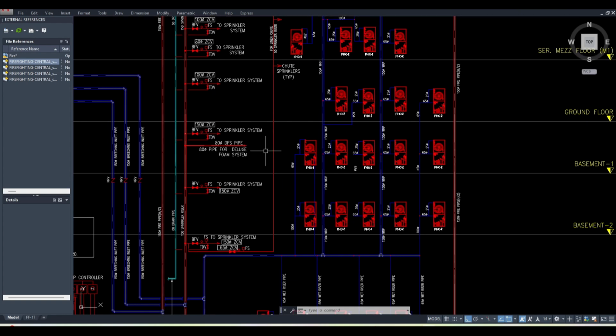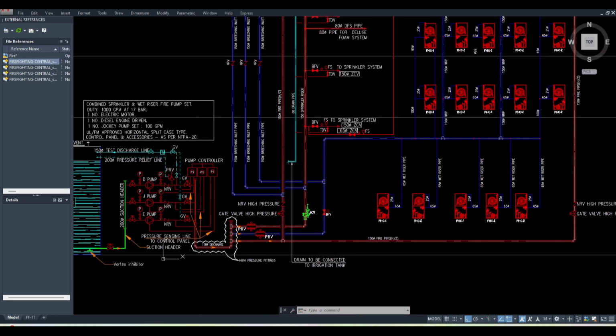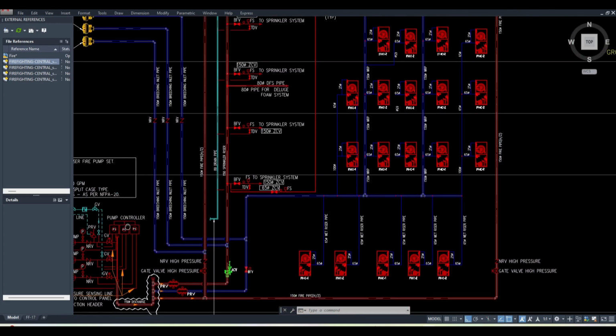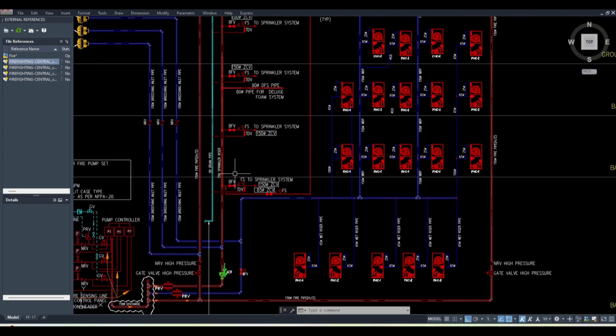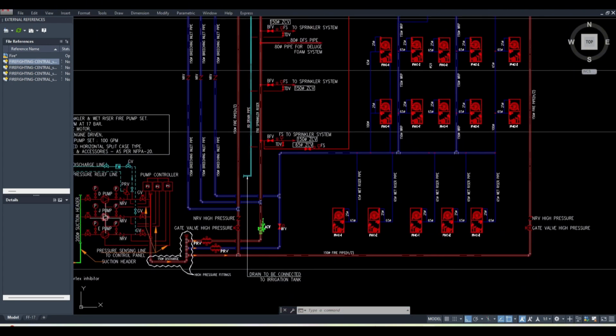How will the sprinkler break? You remember, when the fire happens, the temperature will rise, and once the temperature reaches 68 degrees or 79 degrees, depending on the type of sprinkler, it will break the bulb, and after breaking the bulb it will start spraying the water. Once the water sprays, the pressure will start dropping automatically. The panel will understand that there is a loss of water pressure, so it will start the pump. First it will start the jockey pump. The jockey pump will run to maintain the pressure.